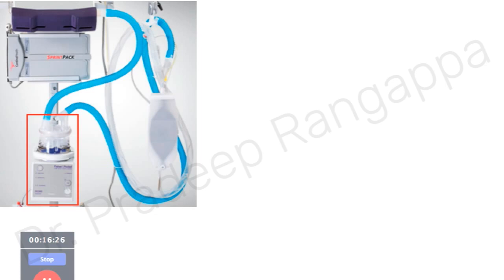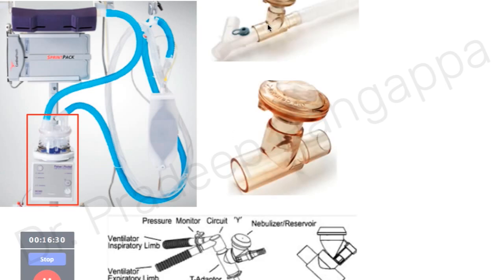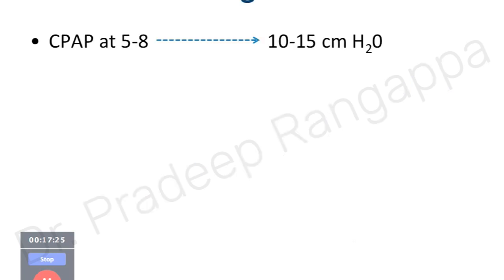Humidification prevents crusting of secretions. The NIV circuit should have ports to connect nebulizers — including vibrating mesh nebulizers or jet nebulizers. Prerequisites summary: a humidifier, shorter and wider tubing, HME filter, battery backup for ventilators, nebulizer connection port, and — for single-limb circuits — a PEEP valve to provide resistance to expiratory flow. An apnea backup mode is also needed. These are the technical checklist aspects for using NIV.